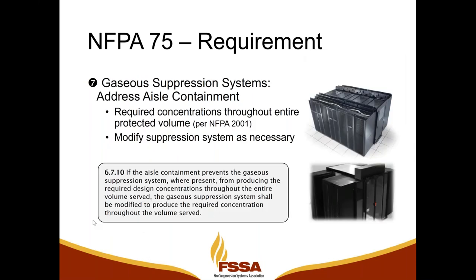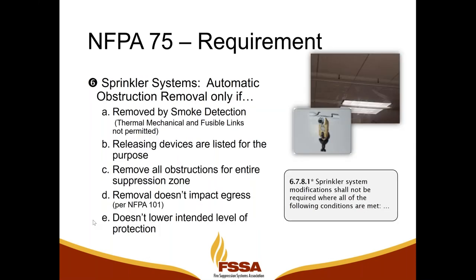And understand, before I leave that slide, automatic obstruction removal is one way that the sprinkler system would not need to be modified for those obstructions. So we would want to remove the obstructions via smoke detection and then allow the existing sprinkler spacing in the data center to remain and not impact the sprinkler spray pattern.